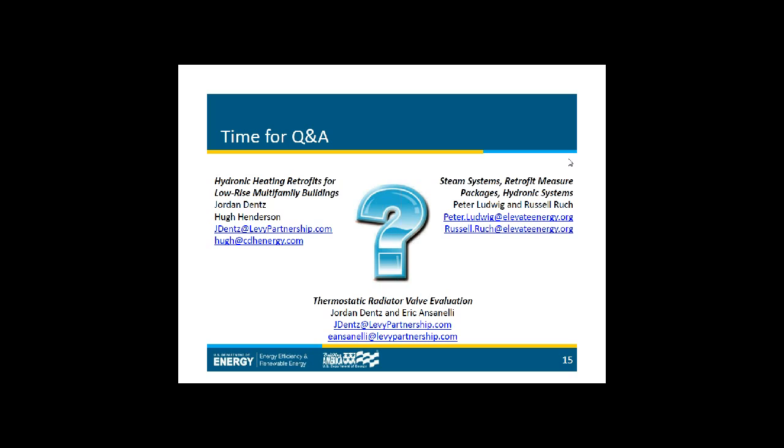Okay, and then the next question for you two is, are the boilers in Building 4 condensing or non-condensing? This audience member was worried about a non-condensing boiler operating with return temperatures lower than 130 degrees. Yeah, so it turns out that in Building 55 they were both non-condensing. In Building 55 they did have a bypass valve that held the temperature higher.